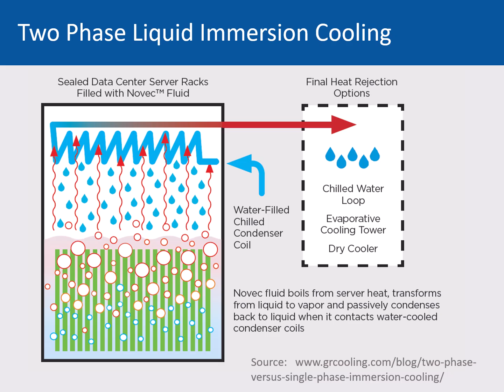Here's a fun little illustration of a two-phase system, like a refrigerant-based fluid that would be bathing the computing equipment, and then that would boil, enhancing the heat transfer - much more enhanced with the two-phase flow. Once the vapor comes out, you have a heat exchanger that pulls the cooling away using your process water.